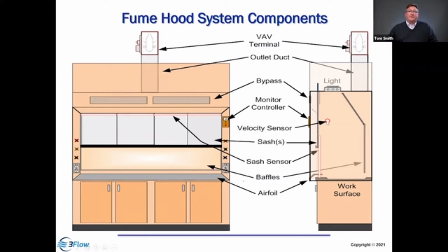We may have some type of velocity sensor and a hood monitor telling the users how the hood's operating. A bypass: when you pull the sash down, it may open up a gap here at the top, allowing flow into the hood. Behind the baffle is the outlet duct and collar, and then some type of controller that's modulating the flow. If it's variable air volume, or if it's constant volume, it's fixed. And so the flow through the hood would be constant in a constant volume hood and variable in a variable air volume hood. Probably kind of self-explanatory.